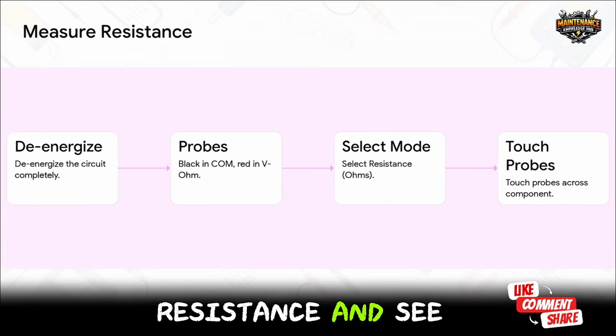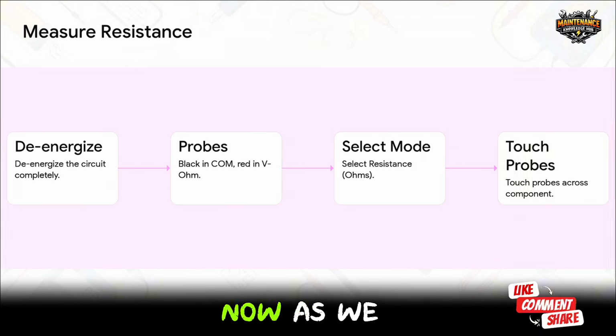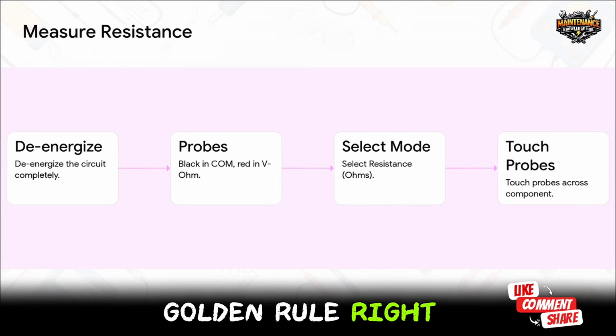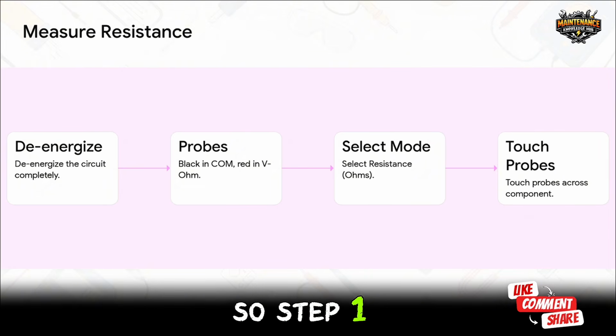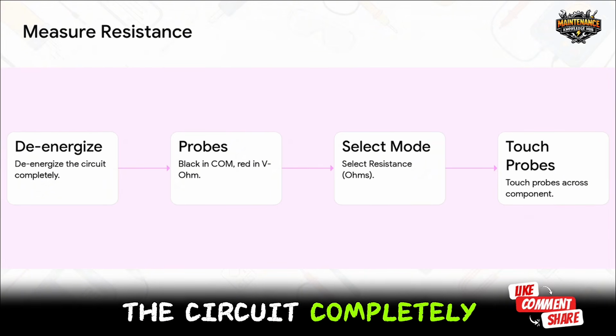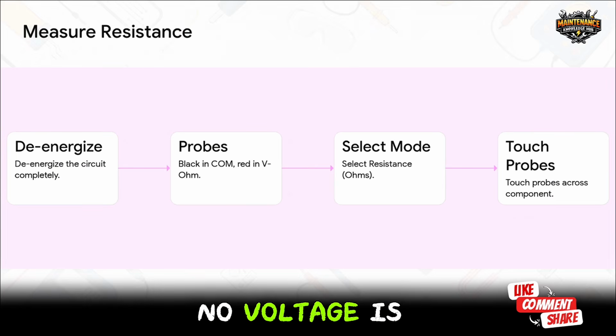Section 4, measuring resistance, ohms. Let's move to resistance and see how this builds. Now, as we prep to measure the resistance of a component, what was our golden rule? Right, never do this on a live circuit. So step 1 is to de-energize the circuit completely. Make sure absolutely no voltage is present.